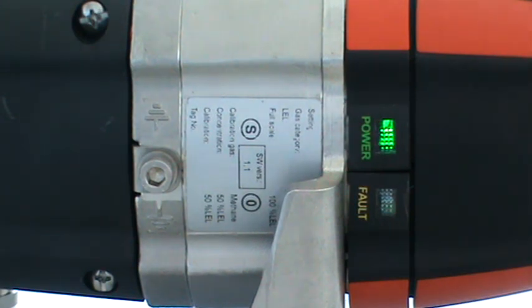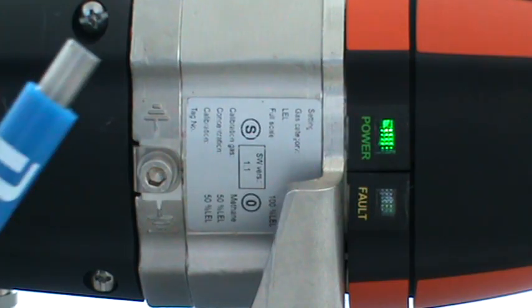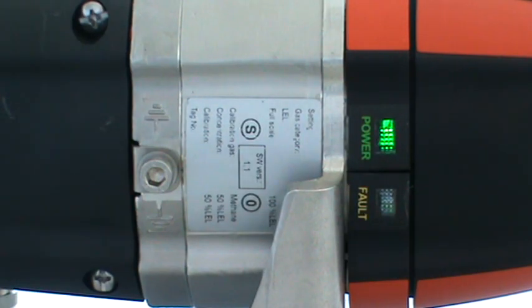With this little video, I now want to demonstrate how to do the 0-point calibration with our gas detector Dräger PIR 7000. At first you need to know that for such a 0-point calibration you just need a simple and inexpensive tool, which is the magnetic wand. And you should remember that during the calibration you need to hit with the magnetic wand 4 times on the PIR 7000's housing. I will show you how it works.